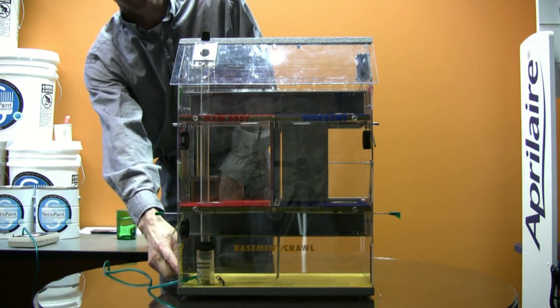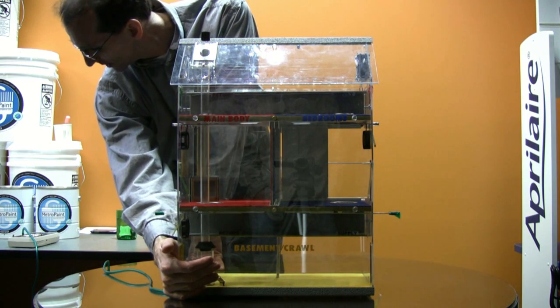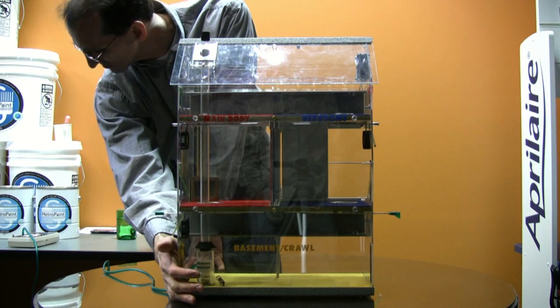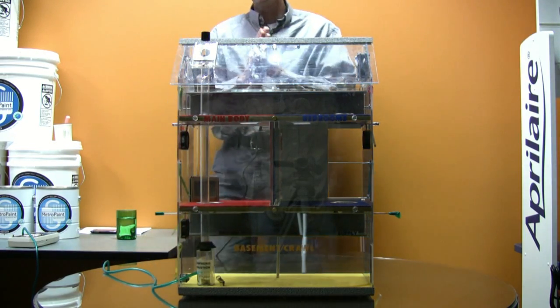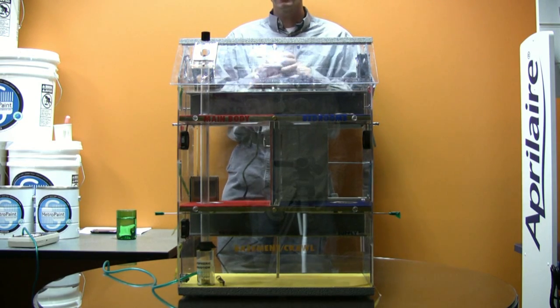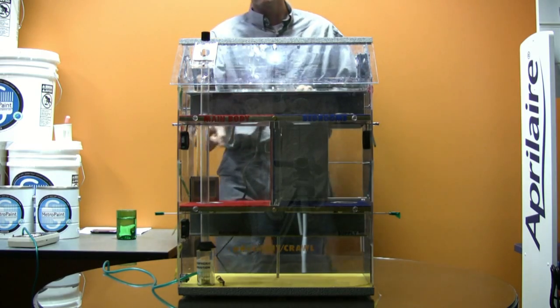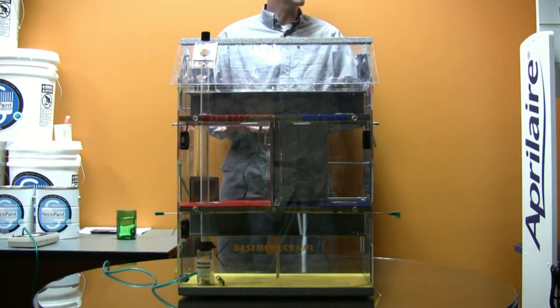It's a ventilated basement. Consider that like a cat door. If you were to cover that hole up, the fan effect would be higher. Now it's coming to negative 0.3 or so. What you really care about when you're thinking about a worst case scenario for that water heater, though, is what other conditions could there be in this house that are going to make this pressure go as low as we can possibly test.